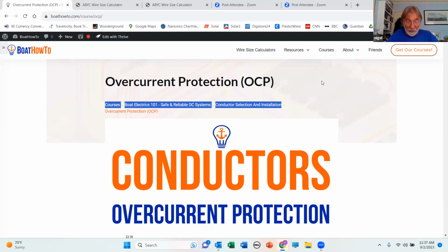So I love lithium ion. I've had it on the boat for years. But my two parameters for lithium ion are, either the battery needs to have been tested and listed. Some battery manufacturers will say they test to a certain standard, but if it's not listed, it doesn't mean it was tested by the people that wrote the standard. So you want it tested and listed to UL 1973, which is by far the most aggressive testing standard in the marine marketplace. If you've got a UL 1973 listed battery, regardless of what kind of mistakes you make or installation errors, it's pretty much impossible to get that battery to go into thermal runaway, and virtually impossible to set it on fire.